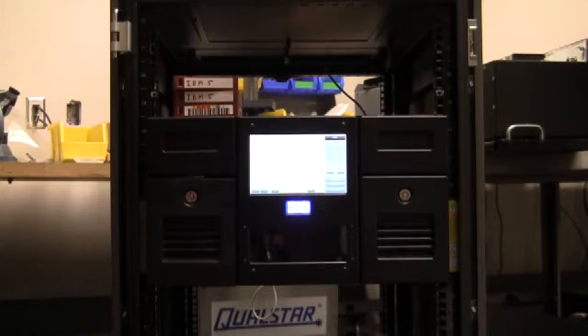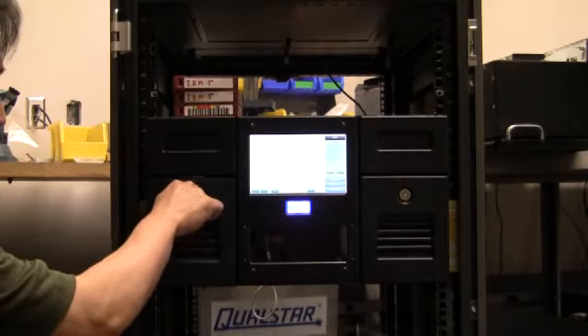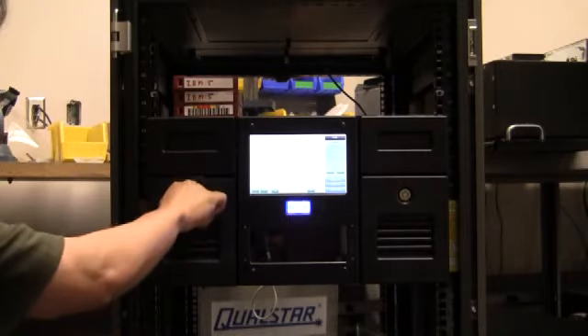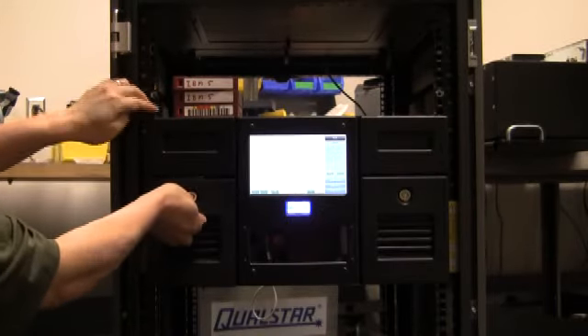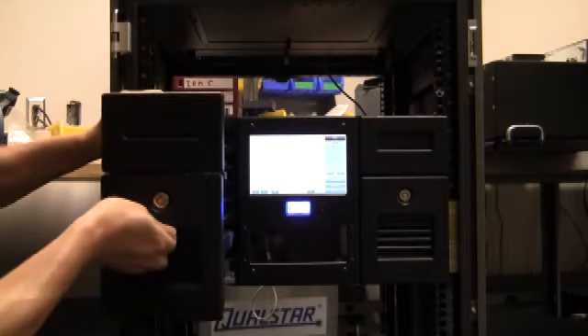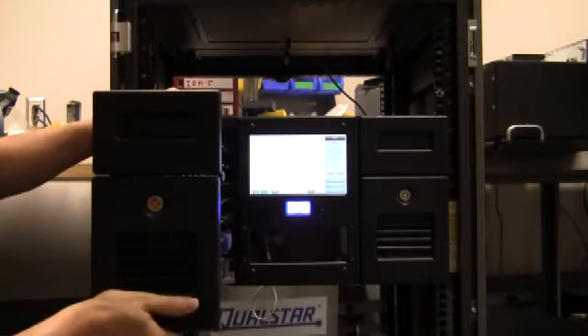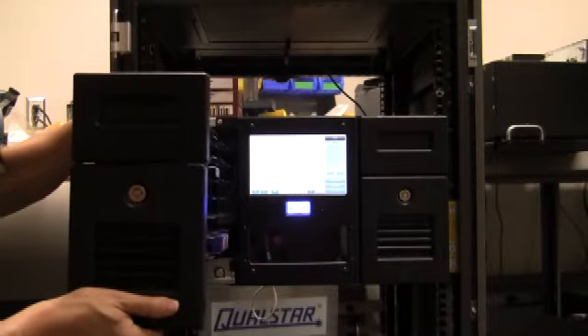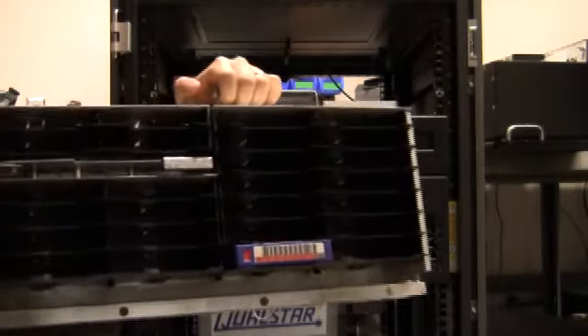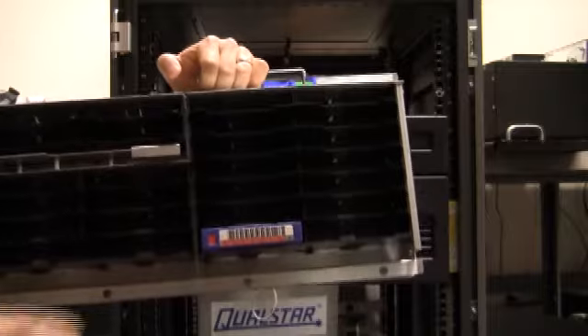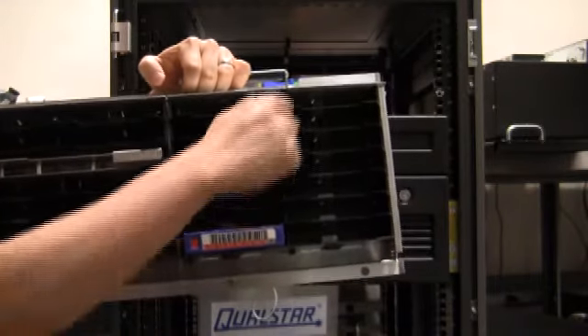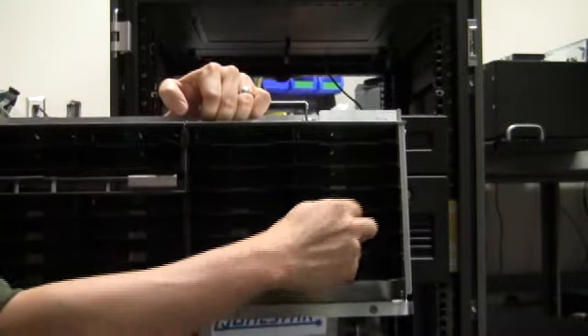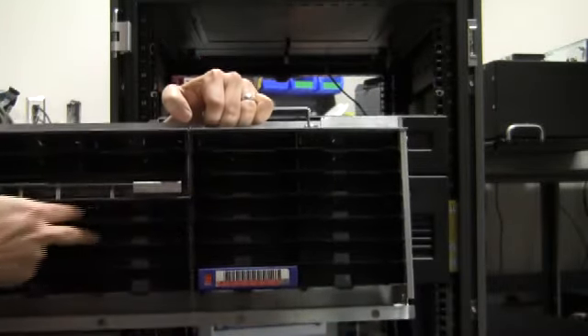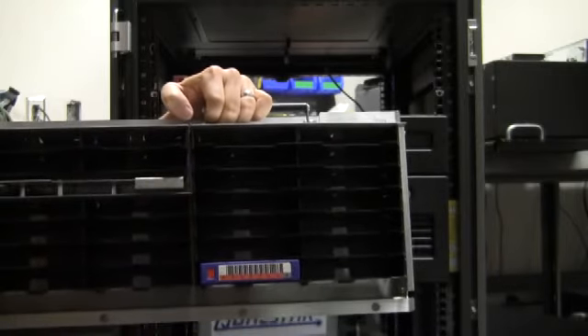To continue with the calibration, you want to go ahead and unlock the left side storage matrix. Once the matrix has been unlocked, slide the matrix out. And then remove any tapes in rows 4 or 5. This is row 1, 2, 3, 4, and 5. So all tapes in rows 4 and 5 must be removed.